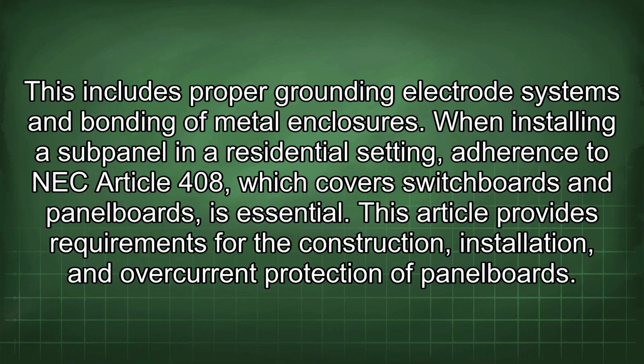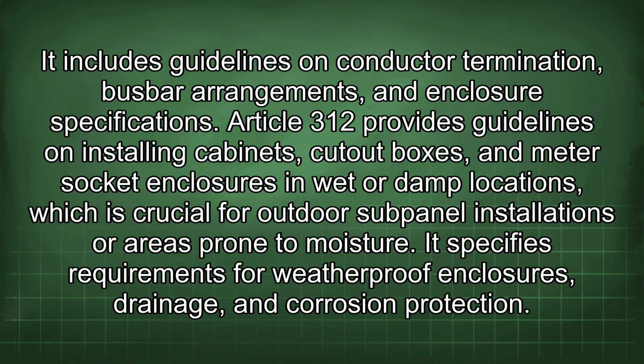When installing a sub-panel in a residential setting, adherence to NEC Article 408, which covers switchboards and panel boards, is essential. This article provides requirements for the construction, installation, and overcurrent protection of panel boards. It includes guidelines on conductor termination, busbar arrangements, and enclosure specifications. Article 312 provides guidelines on installing cabinets, cut-out boxes, and meter socket enclosures in wet or damp locations, which is crucial for outdoor sub-panel installations or areas prone to moisture.